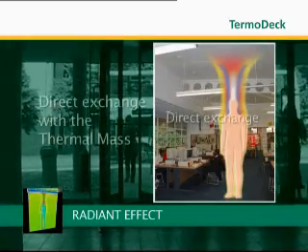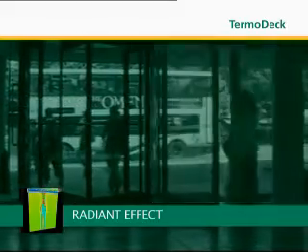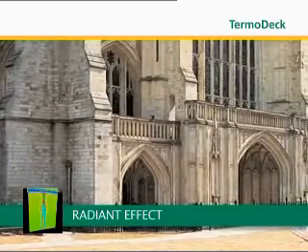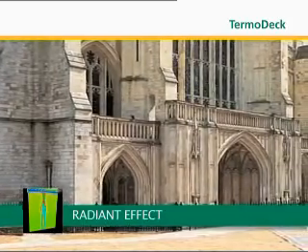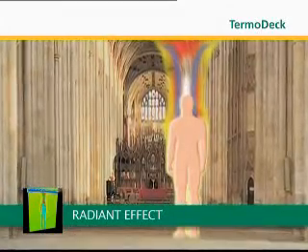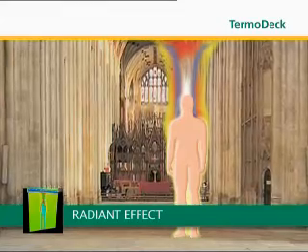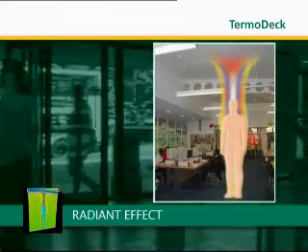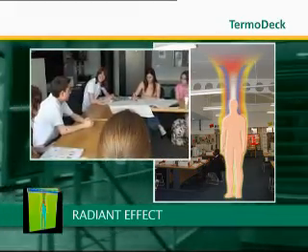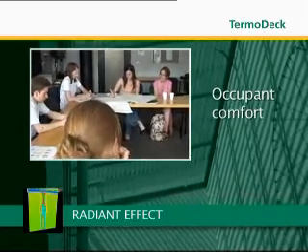And third, radiant effect. The radiant effect is a more direct method of heating and cooling. This principle is the same as that found inside a cathedral on a hot day, where you'll notice instantly how cool it feels stepping through the door, even though the air temperature has not changed. You're cooled by the direct radiant effect of the stone walls. In the same way, heat or coolth is radiated from the concrete slab at the heart of the TermoDeck system, and passive heat exchange takes place directly with the occupants.